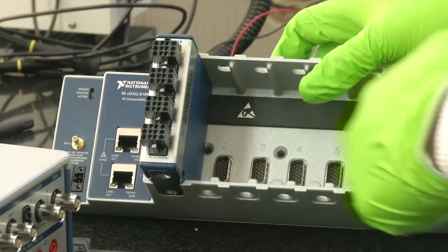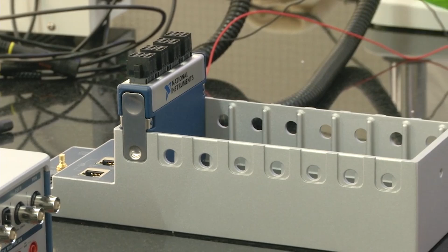So if we have a very sensitive, precise signal conditioning unit, it gives you more accuracy on your measured voltages. So if we have an onboard data acquisition with an onboard signal conditioning unit, it helps very much. How do you place it? If you look at the chassis, it contains a number of channels. Simply select the required signal conditioning unit, or what they call a module, and place it on the appropriate channel. The advantage is that it can be interchanged. It need not be fixed only to that particular channel; it can even be fixed to the last channel, anywhere, wherever it is required.